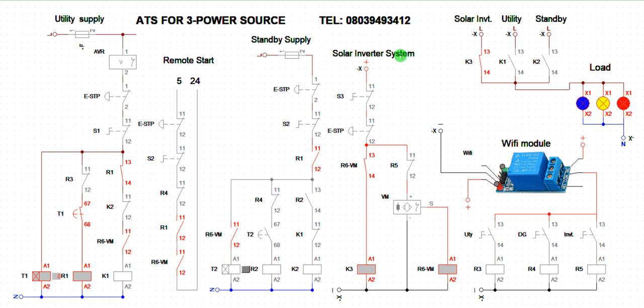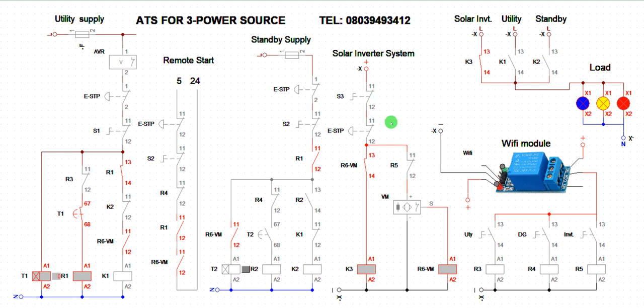Now in the simulation: this contactor belongs to the solar system. If the solar battery goes below 50%, that is the limit — the battery is not expected to go below 50% of its storage. Once you've used 50% of the battery, it needs to be recharged. A voltage monitor watches the battery level, and when it goes below 50%, the system knocks off the inverter so the battery can be recharged.